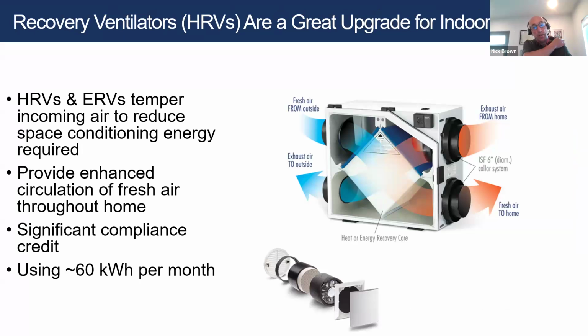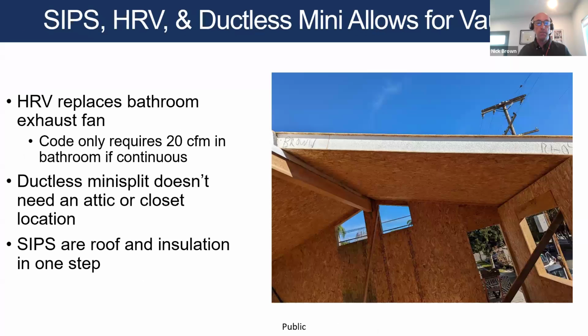As I said before, I really like recovery ventilators. I've got them in the main house and the ADU now, really mostly for improved indoor air quality, but there's also a nice compliance credit in Title 24. Realize they are going to use more electricity than standard exhaust ventilation. You can see the vaulted roof because the HRV replaces the bathroom exhaust fan. In the mechanical code there's a little clause, seldom used - if you have continuous 20 CFM of exhaust in your bathroom, you don't need an extra exhaust fan. So that's what we did with our recovery ventilator - it performs both functions, the whole house indoor air quality and the local venting of the bathroom.